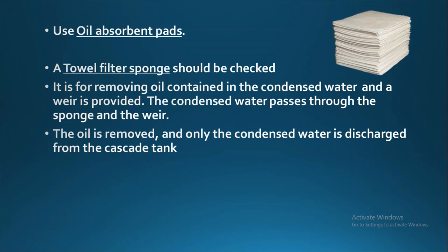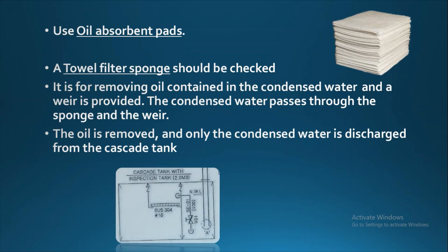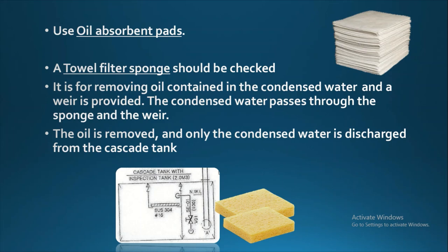Next, a towel-like filter sponge should also be checked. This towel-like filter sponge is provided in the hot well for separating the chambers. It is for removing the oil contained in the condensed water, and a weir is provided. The condensed water passes through the sponge and the weir, and then the oil is removed, so only clear condensed water is discharged from the cascade tank.